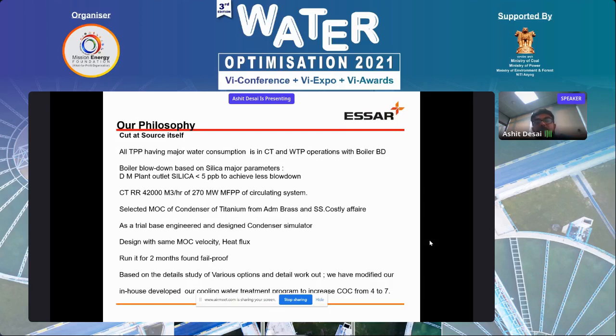Whatever boiler blowdown is generated from the boiler as wastewater is 100% reused for cooling tower makeup. We have laid a line from the boiler blowdown tank to the cooling tower makeup. So there is no wastage of boiler blowdown. It's good water, and compared to 14,000 meter cube of basin volume, it's peanuts to take any contamination. It's good water, basically DM water.